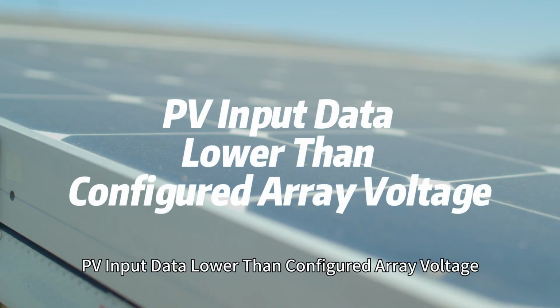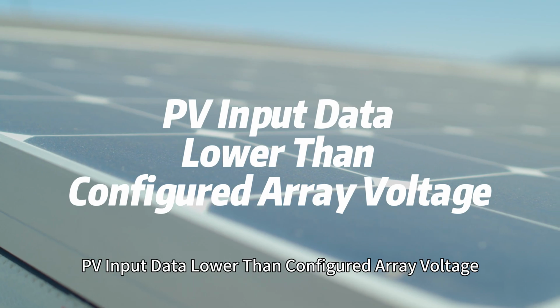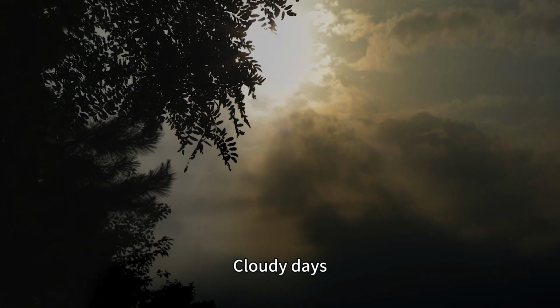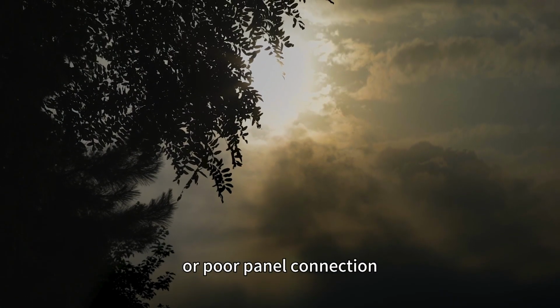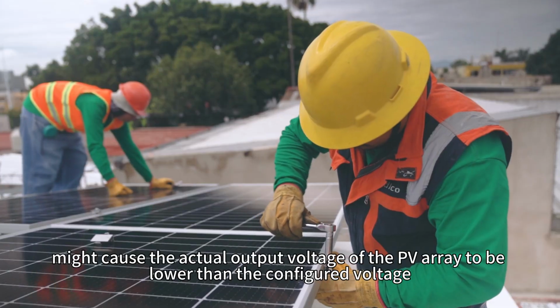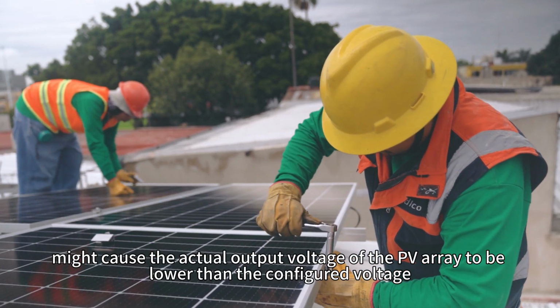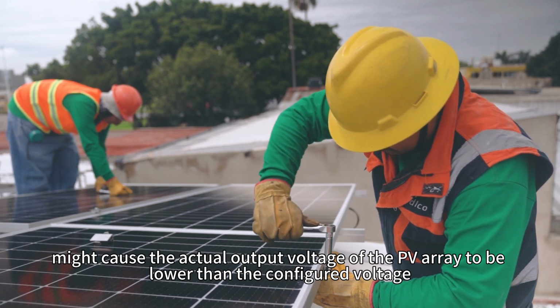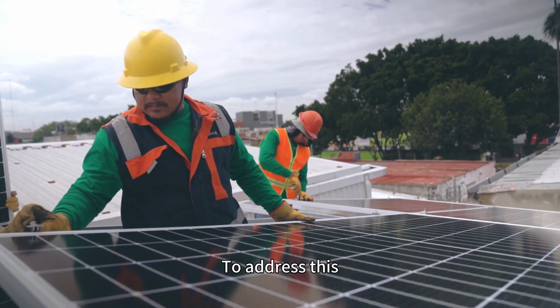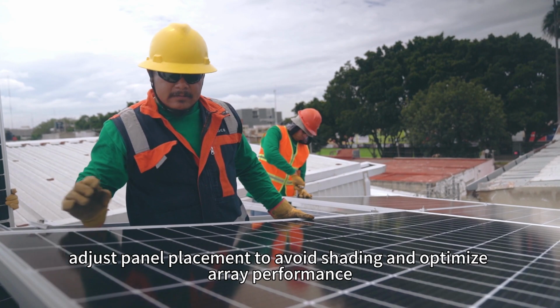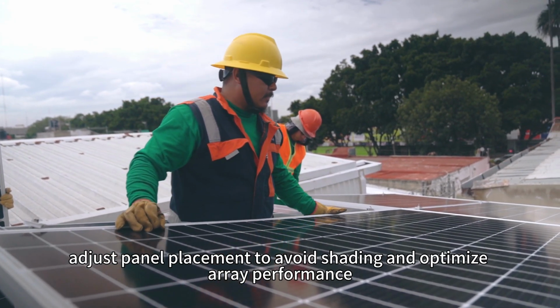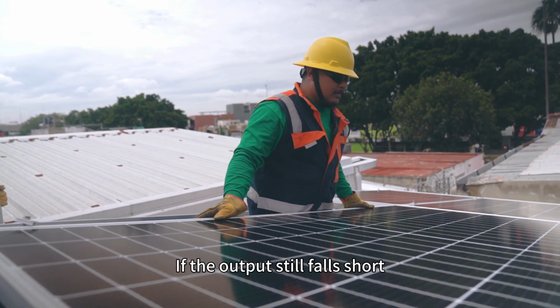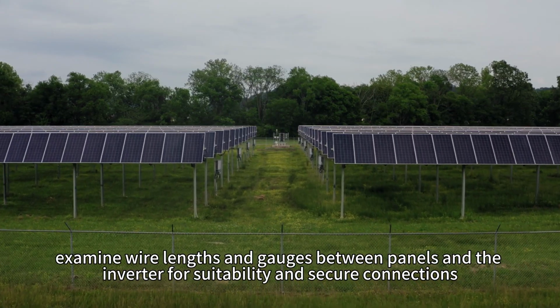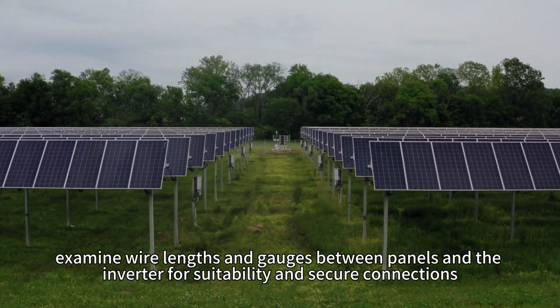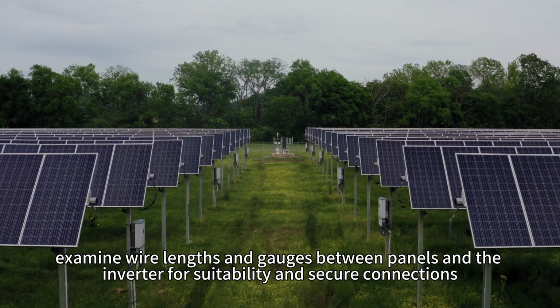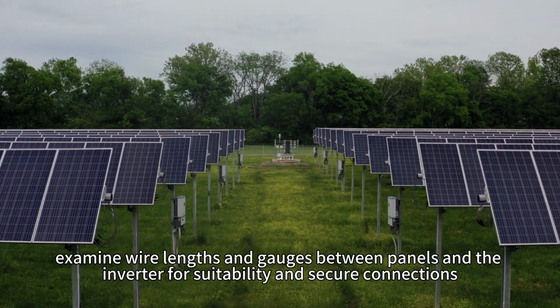PV input data lower than configured array voltage. A cloudy day, shading of photovoltaic panels, or poor panel connection might cause the actual output voltage of the PV array to be lower than the configured voltage. To address this, adjust the panel placement to avoid shading and optimize array performance. If the output still falls short, examine wire length and gauges between the panels and inverter for suitability and secure connections.